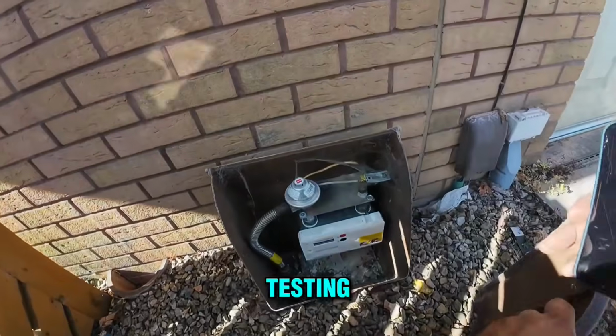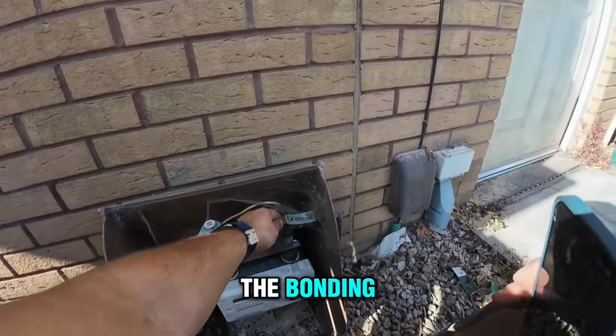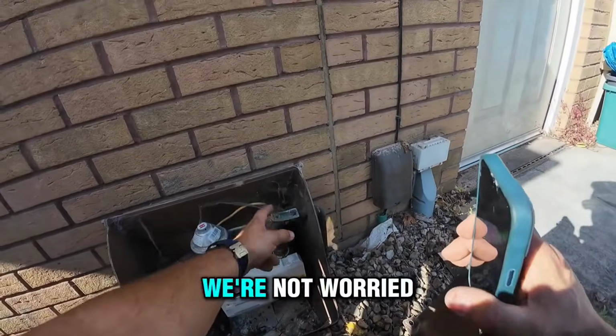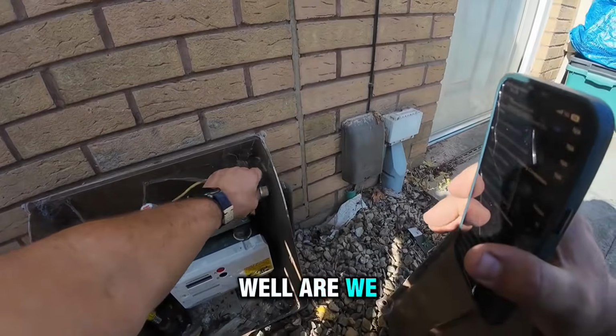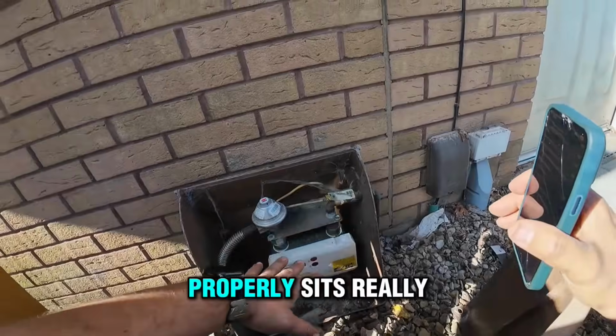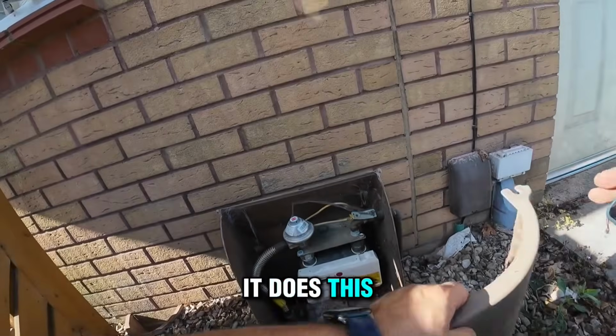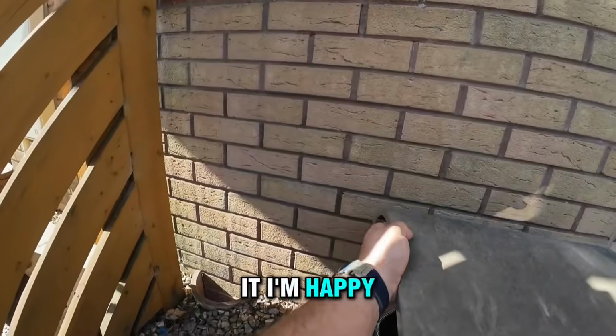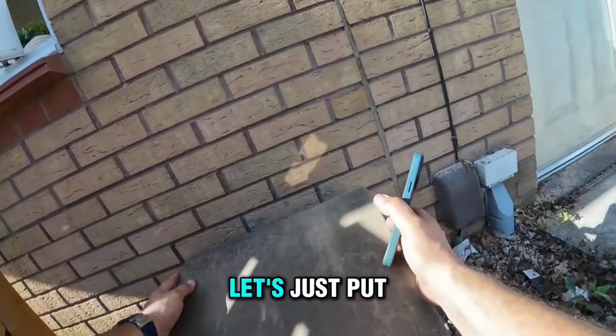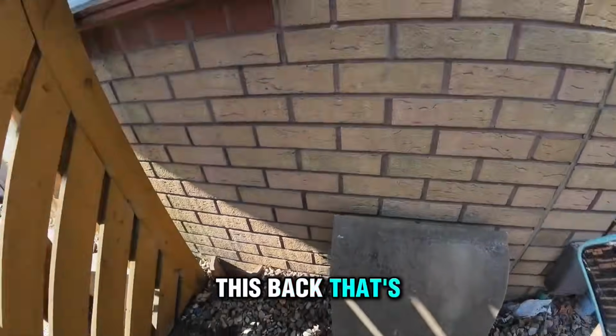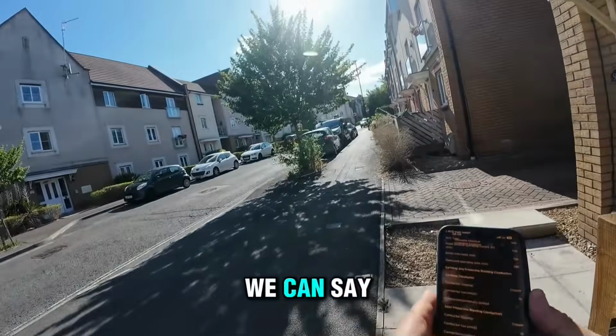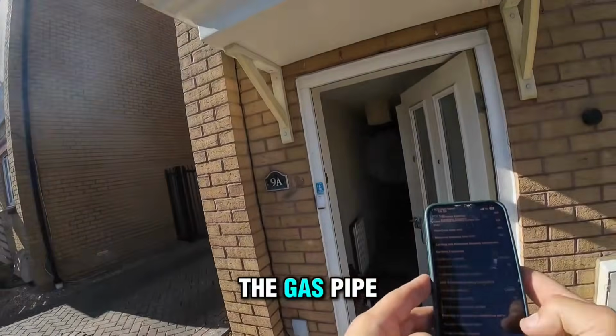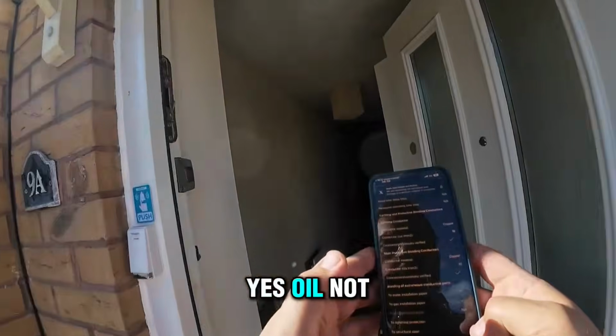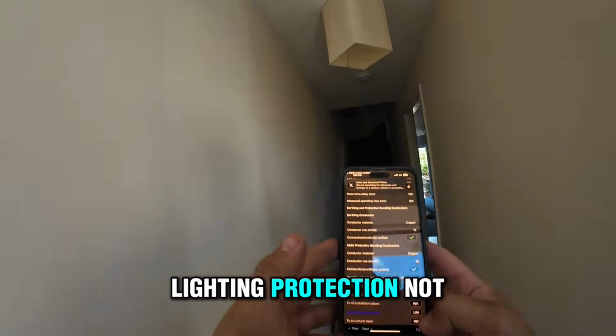As part of the testing, it's also very important to check the bonding. So this is the bonding for the gas. We're not worried about the spiders. Well, are we? Checking if it sits properly, it sits really nicely. It does. There's no wobble in it. I'm happy with that. Okay, let's just put this back. That's okay. We can say that we've checked the installation to the gas pipe. Yes. Oil, not applicable. Lightning protection, not applicable.